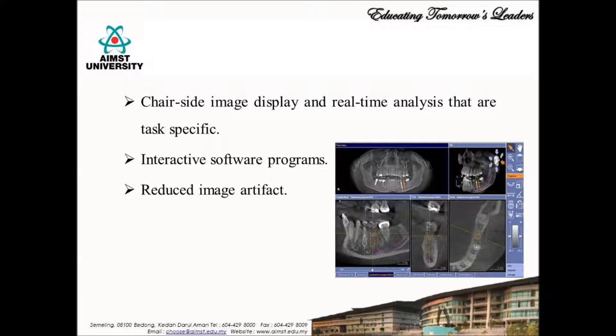Display mode unique to maxillofacial imaging: reconstruction of CBCT data is performed natively by a personal computer. In addition, software can be made available to the user either via direct purchase or per-use license from various vendors. This provides the clinician with the opportunity for chair-side image display and real-time, task-specific analysis. Regarding reduced image artifacts, with the manufacturer's artifact separation algorithm, CBCT images can result in low levels of metal artifacts, particularly in secondary reconstruction designed for viewing the teeth and jaws.